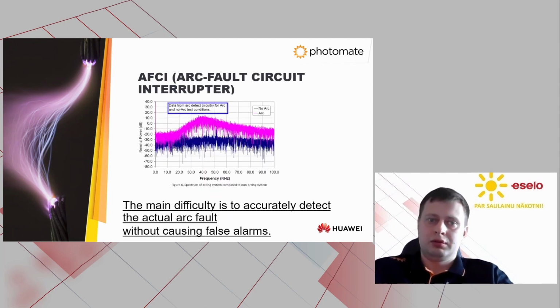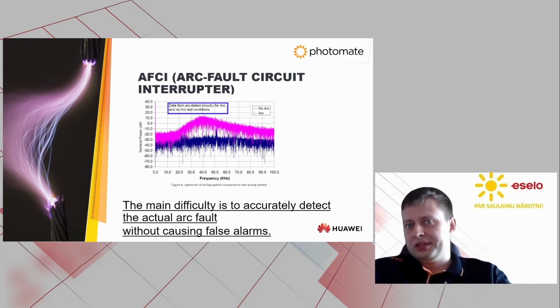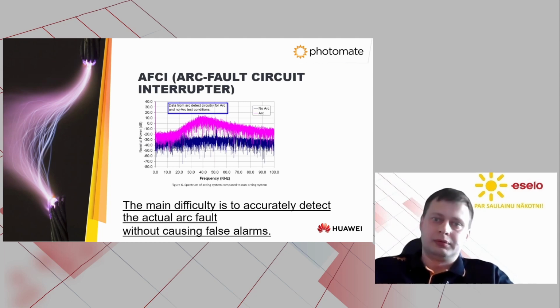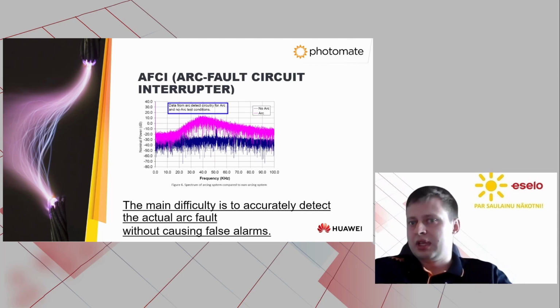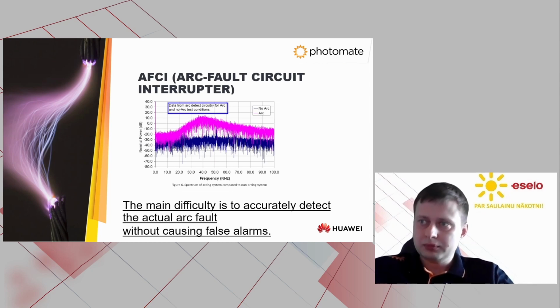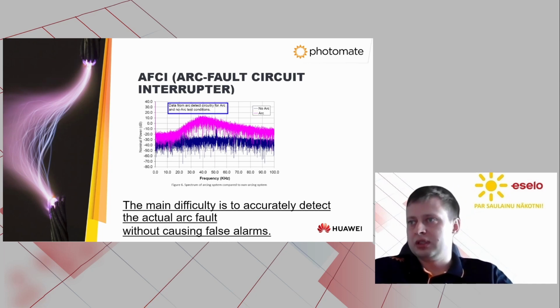So to avoid fires, the AFCI function must be used. AFCI means arc fault circuit interrupter. It is an electronic device designed to detect and interrupt potentially dangerous electrical arcs. An arc results in high frequency noise in the signal. The frequency can be between 10 kilohertz and 100 kilohertz. In the case of an arc, the AFCI will automatically interrupt that circuit to prevent fire. It is worth mentioning, it is not hard to detect an arc, but it is very hard to detect an arc accurately and to avoid false alarms.